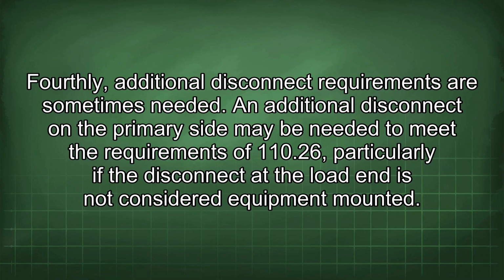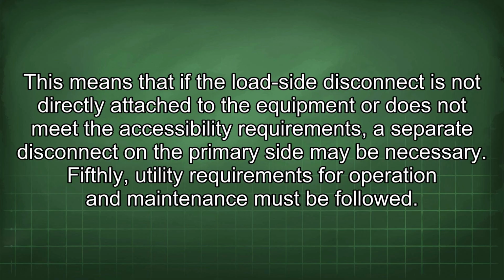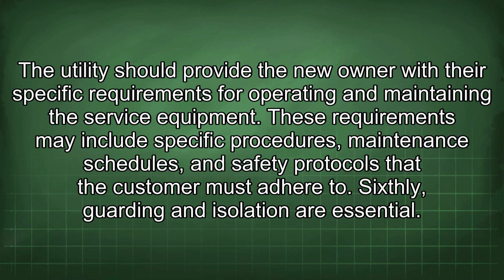110.26. Fourthly, additional disconnect requirements are sometimes needed. An additional disconnect on the primary side may be needed to meet the requirements of 110.26, particularly if the disconnect at the load end is not considered equipment mounted. This means that if the load side disconnect is not directly attached to the equipment or does not meet the accessibility requirements, a separate disconnect on the primary side may be necessary. Fifthly, utility requirements for operation and maintenance must be followed. The utility should provide the new owner with their specific requirements for operating and maintaining the service equipment. These requirements may include specific procedures, maintenance schedules, and safety protocols that the customer must adhere to.